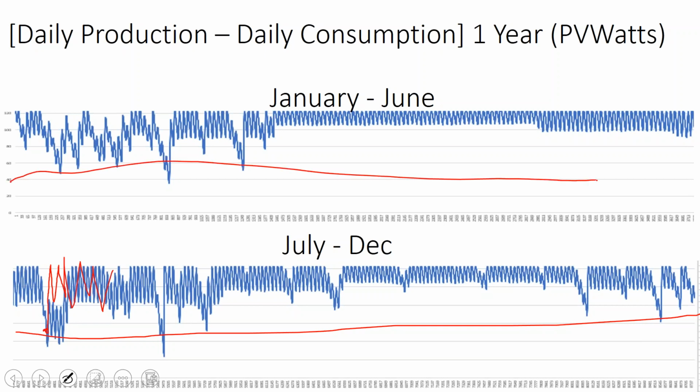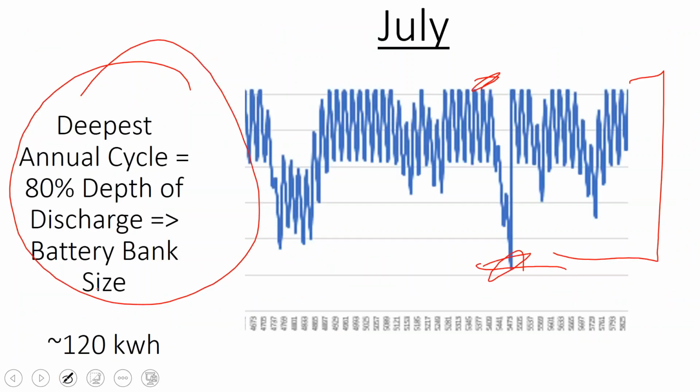And we're going to be using it 1, 2, 3, 4, 5, 6, 7, 8, 9, 10, 11 times a year, maybe 12 times a year, just to keep the batteries topped up. That's independent of the maintenance charging cycle, although they can be coincidental. When you need to do more battery maintenance is when you're more deep cycling these batteries. So you can time them at the same time. And so what that means is he's going to be using his generator about 12 times a year.